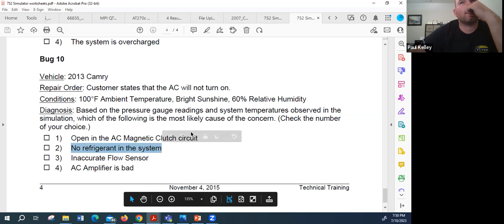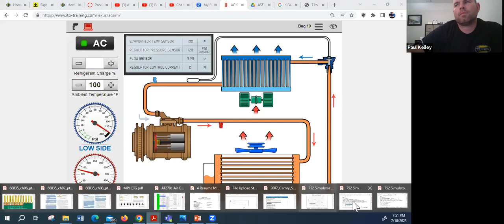Maybe. All right, if it's a maybe, what's our static pressures? The same. If there's no refrigerant, what would these static pressures be? The same as when it was off, low. They would be the same because the compressor's not running, but they'd be low or close to zero if there's no refrigerant at all. I think we can eliminate that one because our static pressure tells us so.